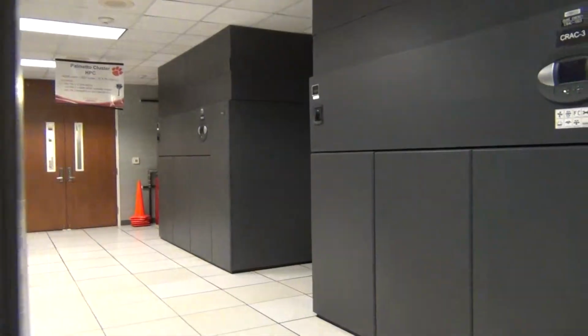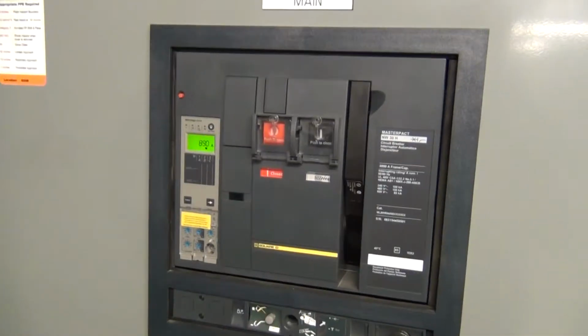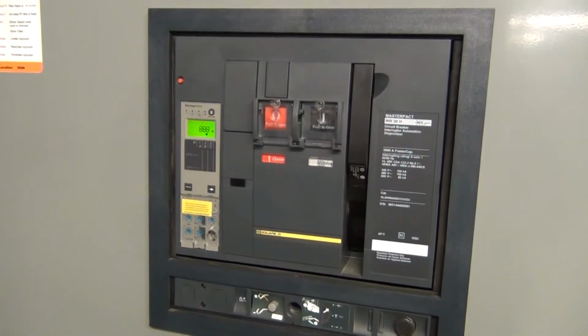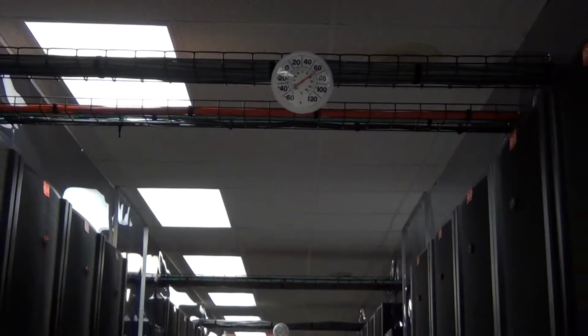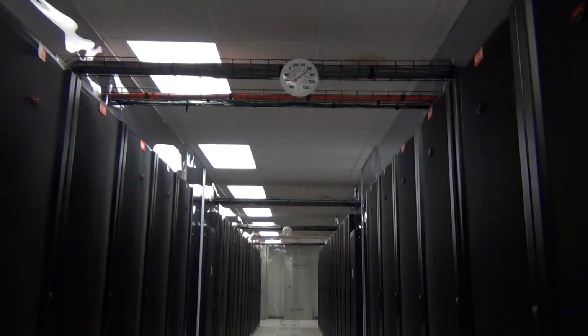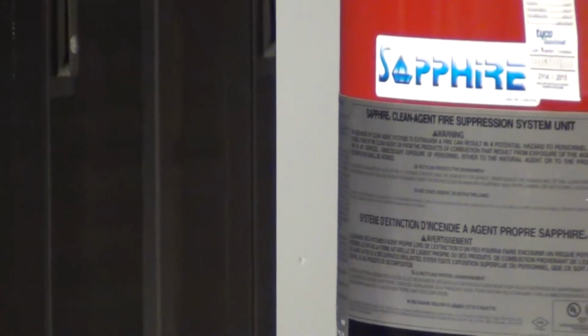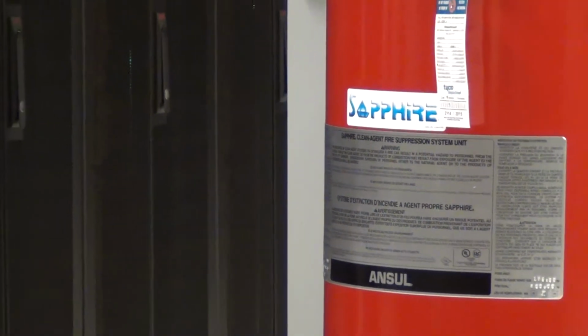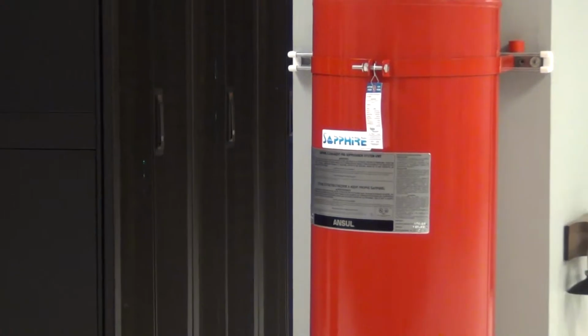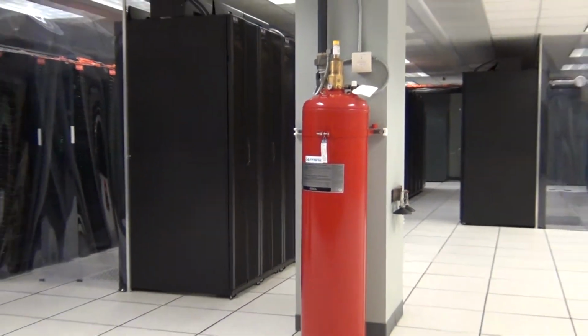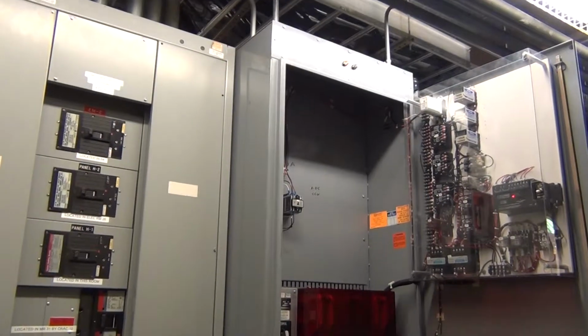Due to the ever-increasing density of high-performance computing equipment, we've put in a tertiary loop that runs chilled water above the dew point through radiator racks on the rear doors, so that we trap and neutralize the heat at the source. Right now the facility is about 60% utilized, which gives us growth capacity, but that leads to a problem.